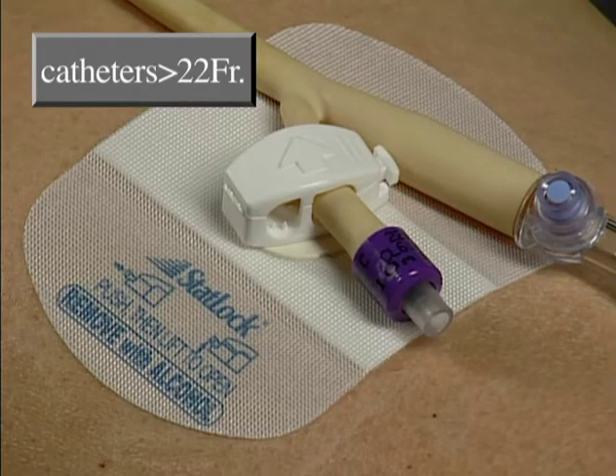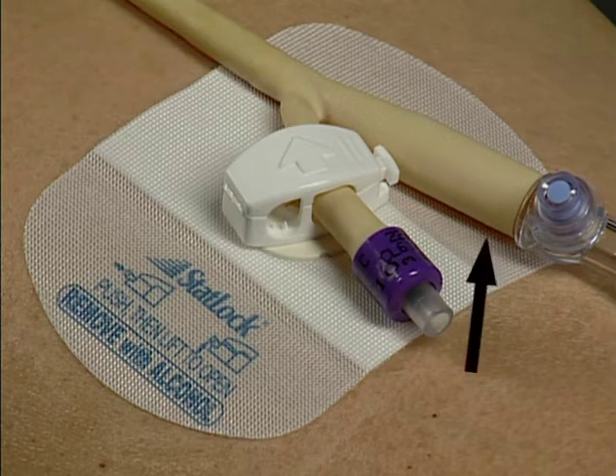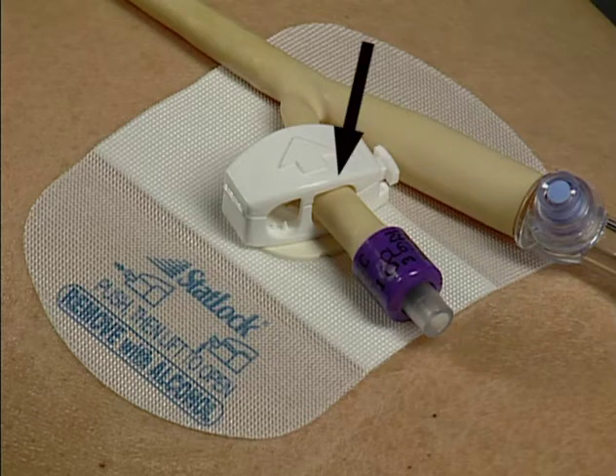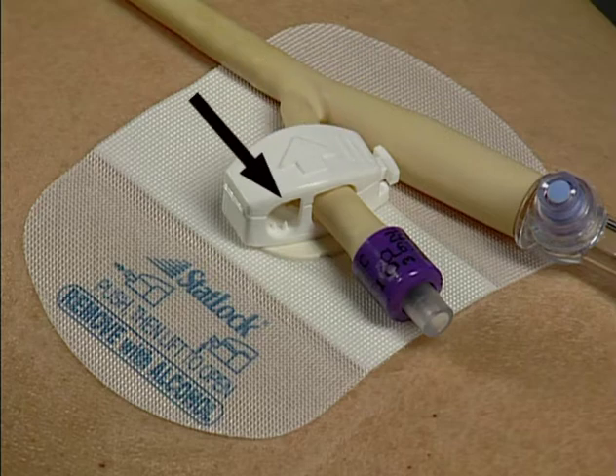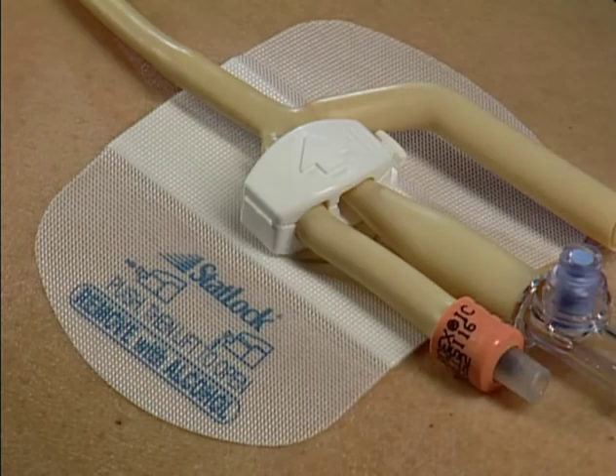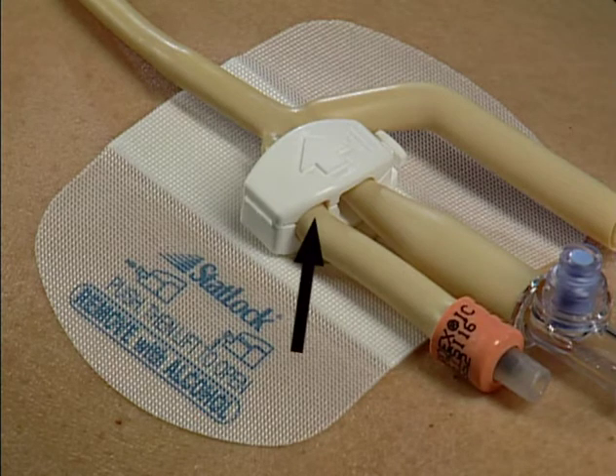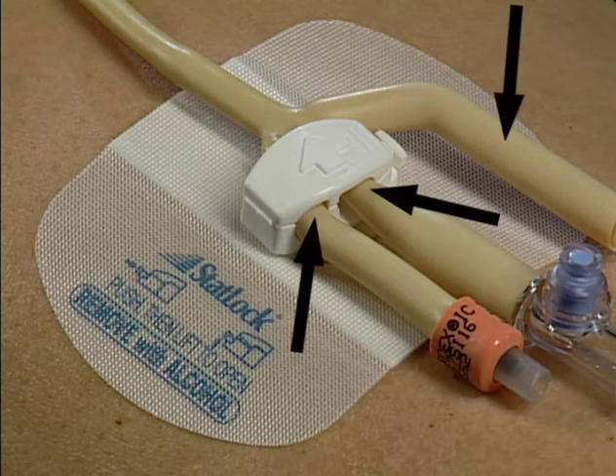For catheters larger than 22 French or catheters that do not fit easily into the retainer, place the fluid channel of the catheter outside the StatLock device retainer and secure the balloon sidearm in whichever channel provides the snuggest fit. For most trifurcated Foley catheters, simply capture 2 of the 3 channels within the StatLock device retainer and allow the third arm to sit outside.